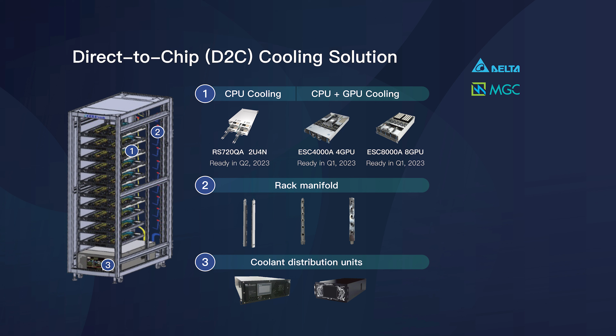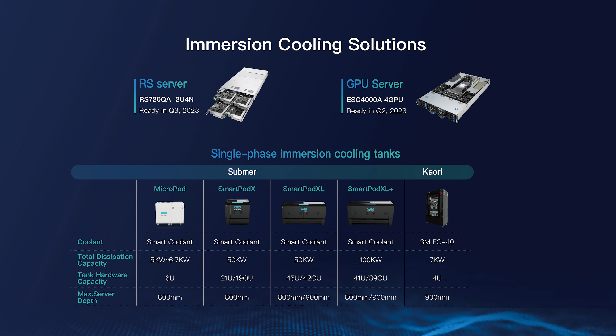The tank hardware capacity of Submer ranges from 6U to 41U, supporting dissipation capacity from 5,000 watts to 100,000 watts, using a hydrocarbon-based solution dubbed Smart Coolant. Alternatively, Kaori provides a customized tank filled with a fluorocarbon-based coolant. Smaller tanks in the 4U or 6U range are typically used for edge applications, while larger sizes are suited for data centers.